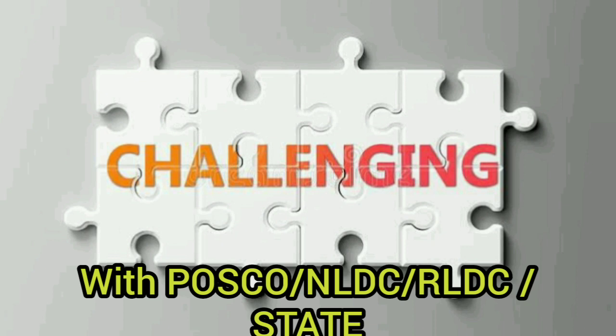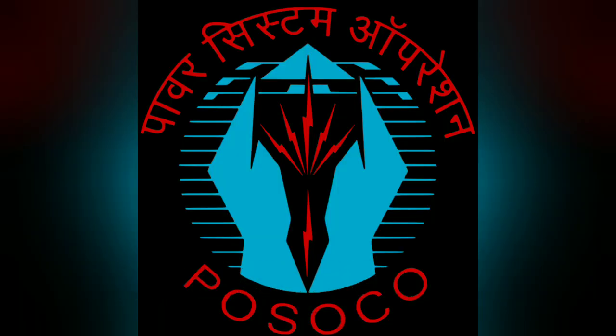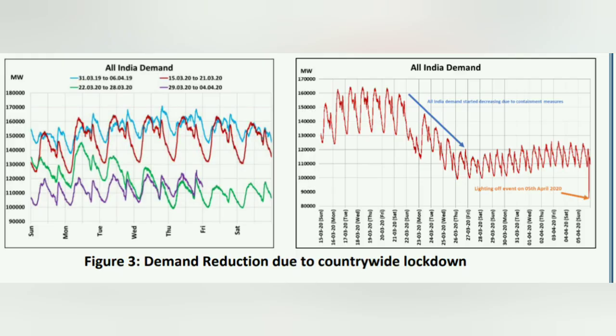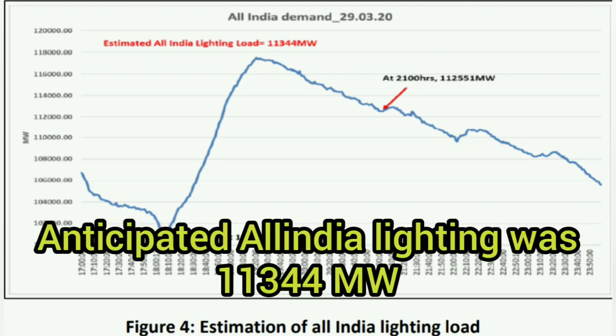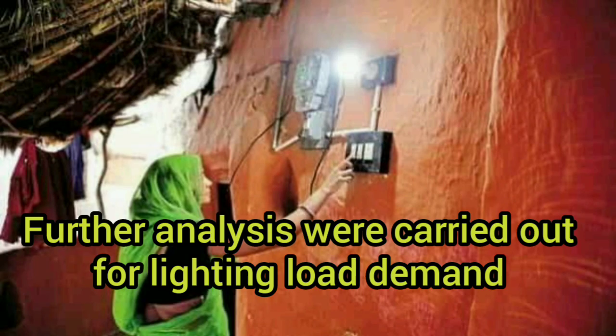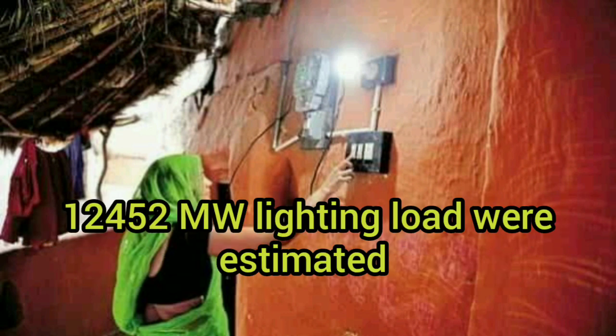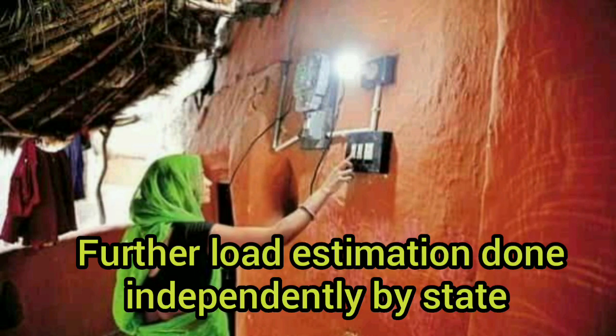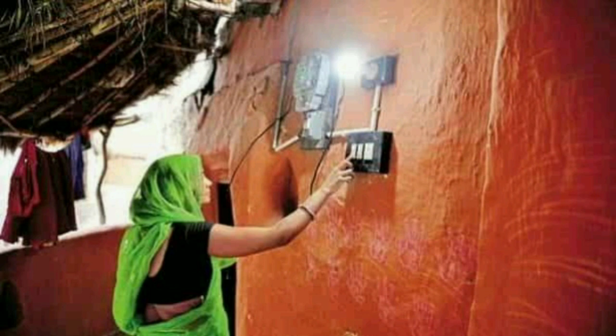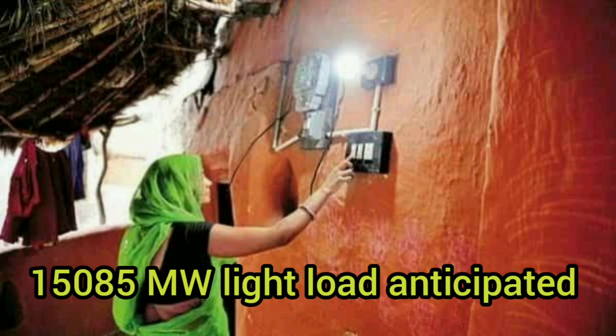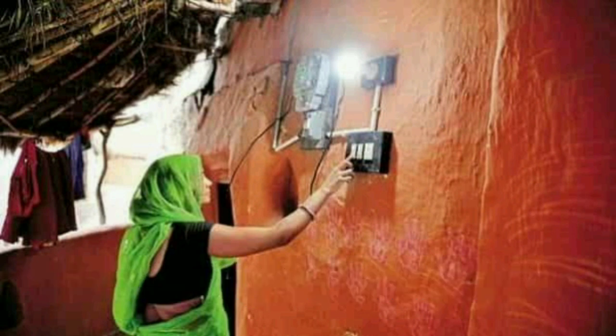So various meetings were called for POSOCO, NLDC, RLDC. Firstly they estimated the load reduction during the 9 minutes of the light off event. Prior to the light event, all India demand was already reduced by 30 to 40 gigawatt. Based on the analysis, the anticipated all India lighting load reduction at 9 o'clock was estimated at 11,344 megawatt. Even after this, an independent household load consumer analysis in India was carried out, and they assumed a lighting load of 12,452 megawatt. The same exercise was also done by the SLDCs separately, and the load reduction anticipated was around 15,085 megawatt. So it was in the range of 12 to 15 gigawatt.